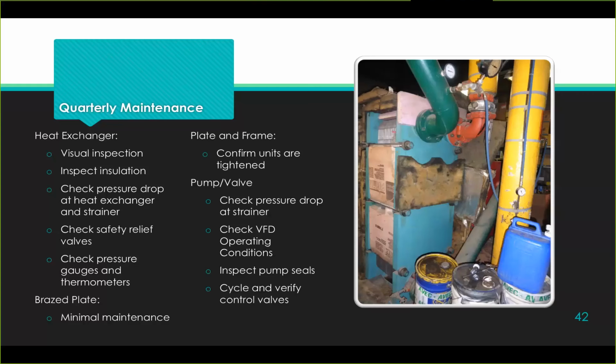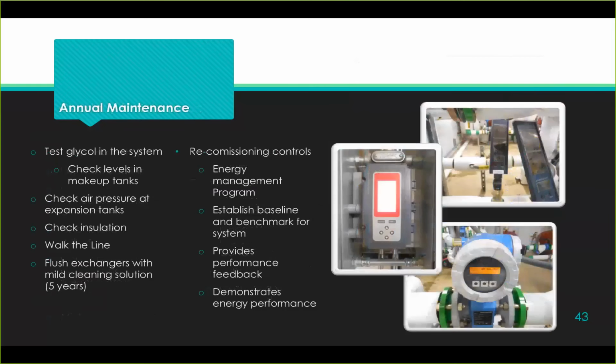You're just going to check pressure drops at strainers. You might want to verify your VFD is operating as it's supposed to be. You might want to inspect the pump seals. You might want to cycle and verify your control valves are operating. The maintenance is pretty straightforward. Annually, again, things that you should be doing normally anyway.